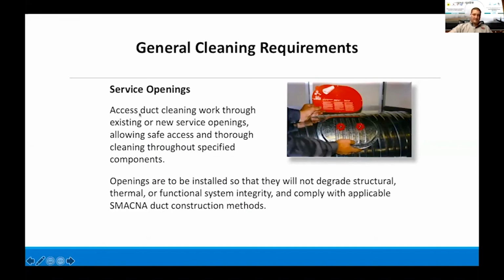Service openings. Access duct cleaning work through existing or new service openings, allowing safe access and thorough cleaning throughout specified components. Openings are to be installed so they will not degrade structural, thermal, or the function of the system's integrity, and comply with applicable SMACNA standards and duct construction methods. SMACNA is another HVAC organization. A good way to explain this is that SMACNA standards are a way that we conform to making sure that ductwork is installed properly. And so in certain areas, these service openings, this is a door that they use. It's specially made for this kind of duct, so that when we cut into it to clean it, we have a way of putting it back together.